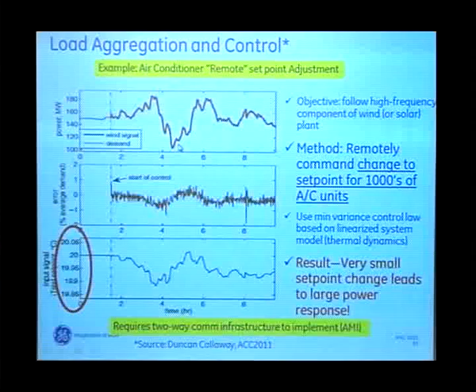What's exciting about this work is that you can actually vary the production of power to match demand - this is the error between the demand and the power required - simply by changing the set point of a lot of little plants out there. In his example, he simulated 1,000 air conditioning units in a conventional residential housing setting. The important takeaway isn't how he did it, but that with very small set point changes - this is the set point signal in degrees C, the set point temperature for the space - changes you would hardly notice in terms of comfort, you can get enormous variation in the power load produced.